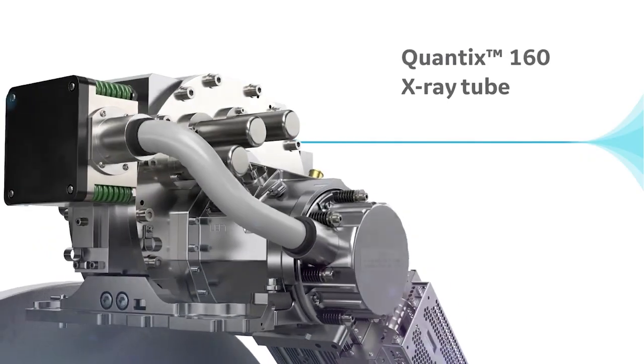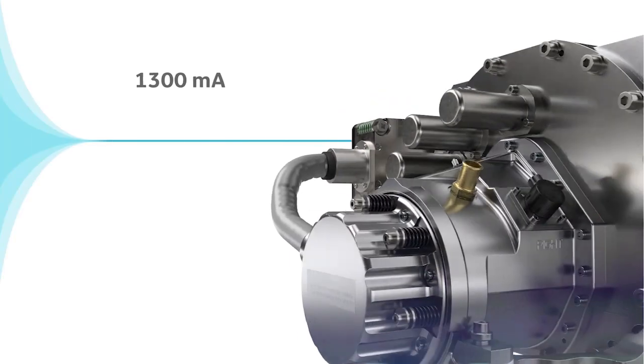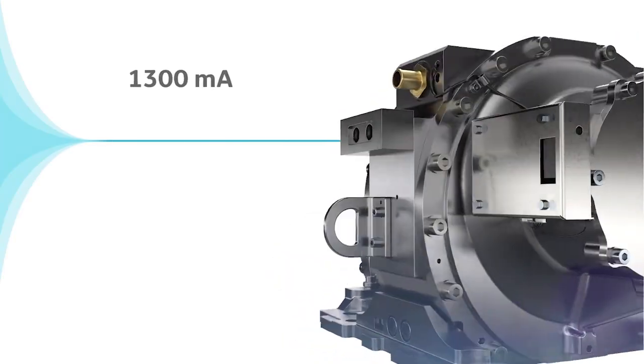And finally, the Revolution Apex comes with the new Quantix 160 tube, achieving up to 1300 mA. With this high-powered tube, you will get uncompromised image quality for your bariatric patients and allow for low kV imaging, so you can reduce radiation dose to your pediatric patients and contrast dose to your patients with renal insufficiencies. The Revolution Apex is the only CT scanner on the market with this combination of high-powered tube and wide coverage detector.